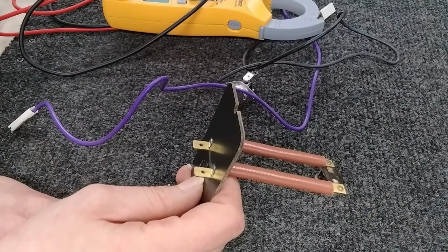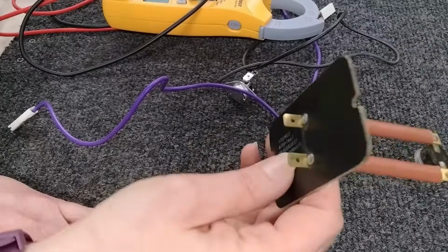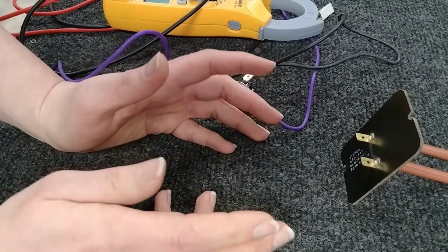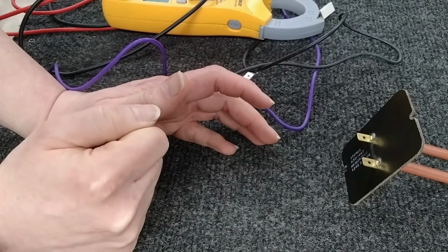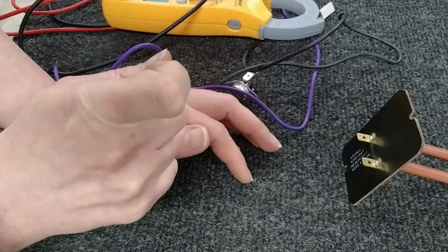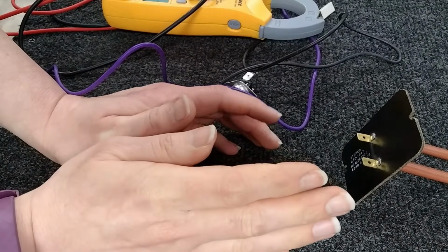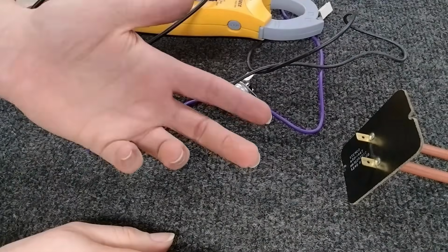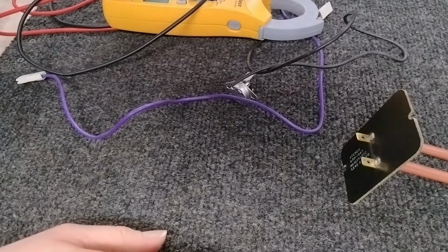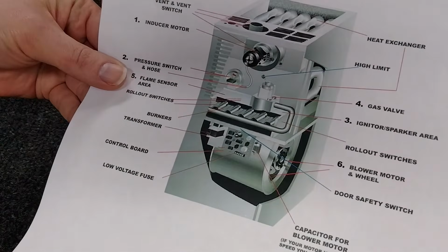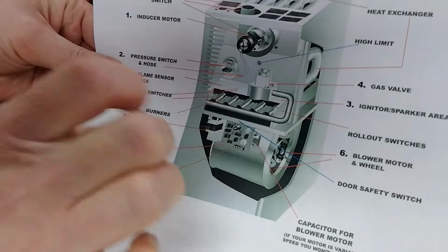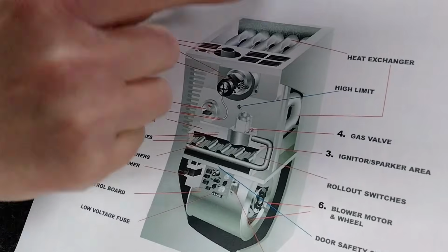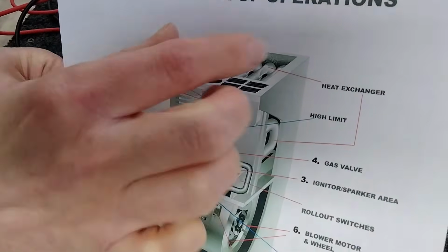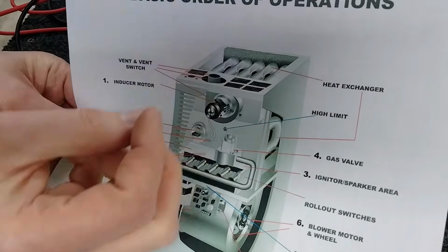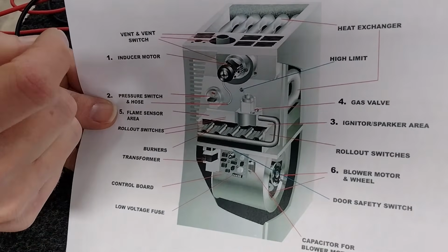Probably, if we think statistically, that's not going to be the case, which, what does that mean? Okay, really frustrating when, again, this thing is opening and your board is saying that it's opening, but it doesn't mean your board is bad. It means that the high limit is doing its job and your furnace cabinet is overheating. What that means is you probably have low airflow here. And the most common reason for low airflow is your evaporator coils, which we can't see on this page. It's going to be in a separate encased box up here. A lot of you have A-shaped coils, some N, and maybe a slant depending on if you've got a wall unit, something like that. What that means is you need to clean your evaporator coils.